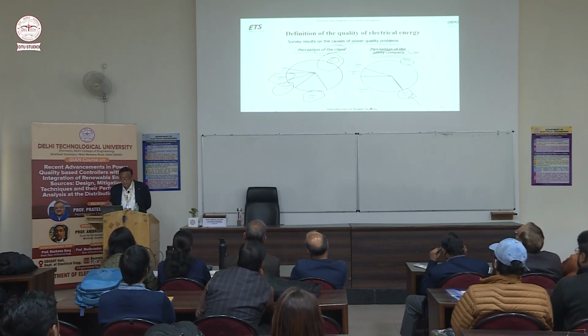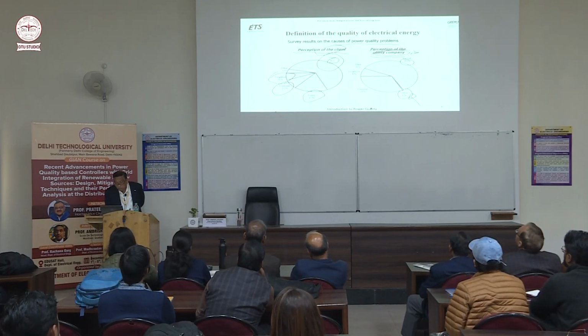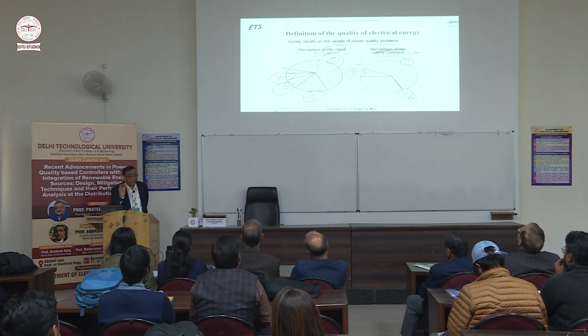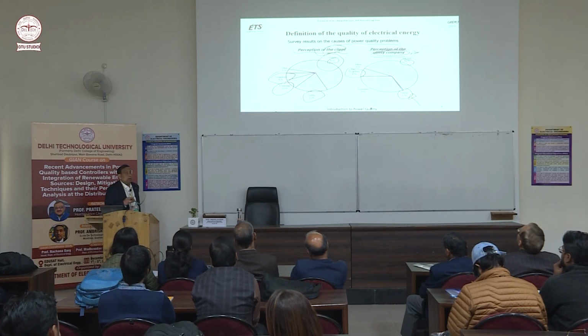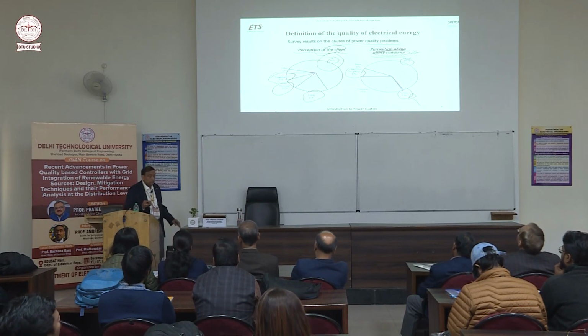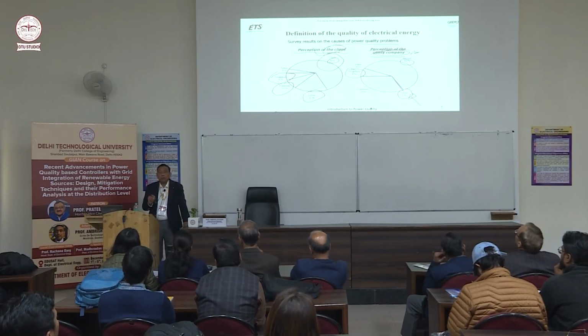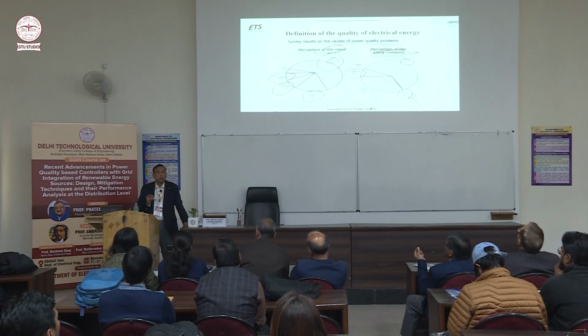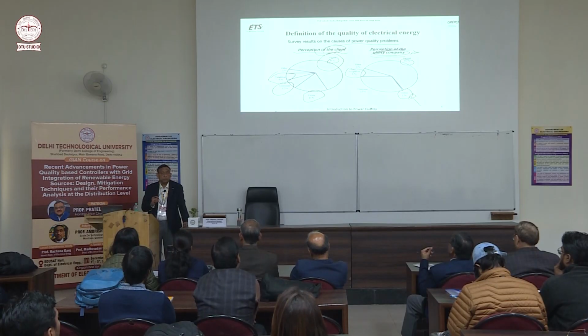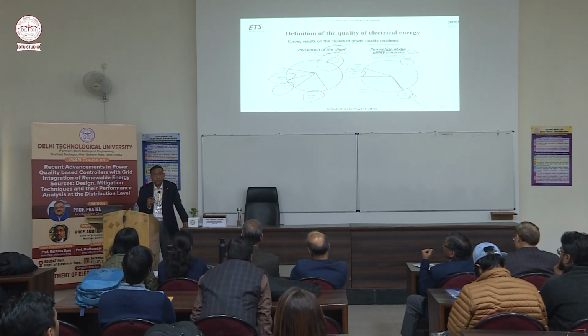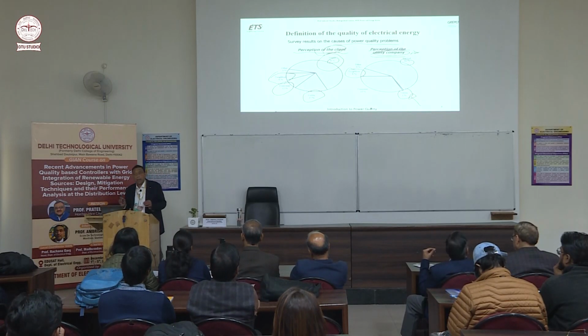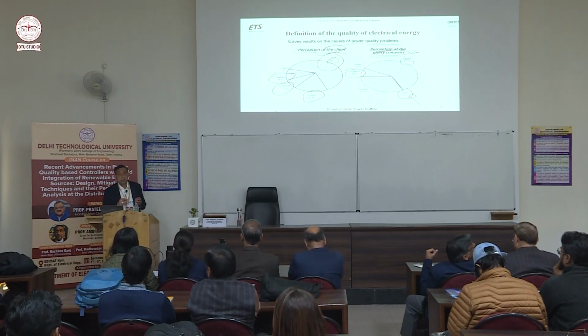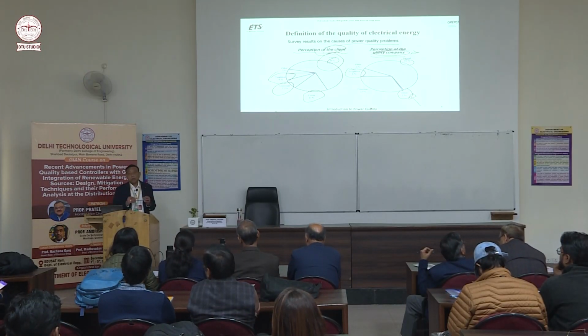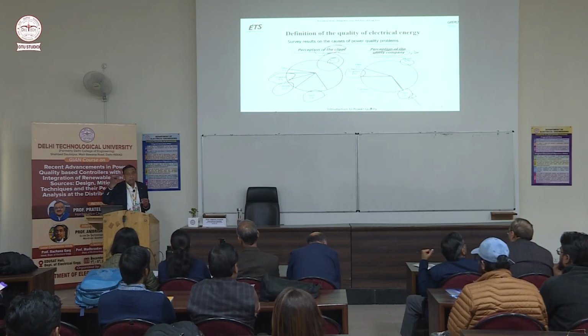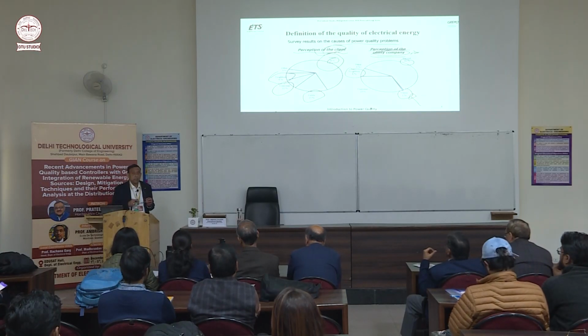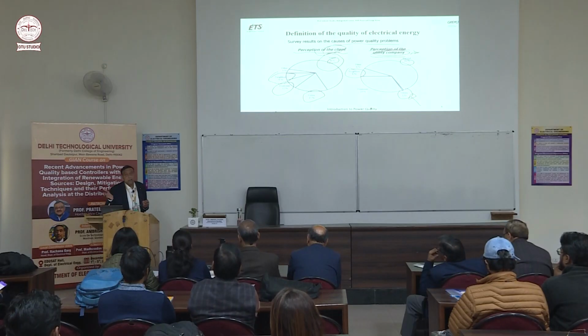Neighbors, 8%, according to the clients. What can the neighbors cause? Sometimes there is one client which has a linear load with reactive power, and it has put a capacitor bank at the entry of the industry to improve the power factor. But there is another neighbor, some industry nearby, which is generating harmonics.